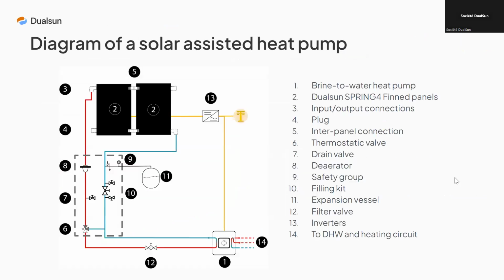Then here you can see the schematic diagram, which is as follows. So you have the two main elements, the hybrid panels on the roof connected to the heat pump. Inter-panel links to hydraulically connect the panels together, and inlet-outlet kit to connect hydraulic lines and create a closed circuit. Between these two elements, we set up the PVT heat pump station composed of an important element, which is here in 6, the thermostatic valve, which protects the heat pump because we have a minimum and a maximum evaporator inlet temperature within which we have to stay to avoid sending glycol at too high a temperature. The valve therefore allows you to mix in cold glycol water to limit this temperature.